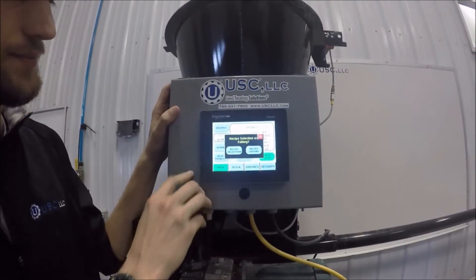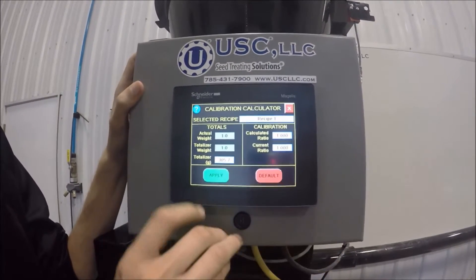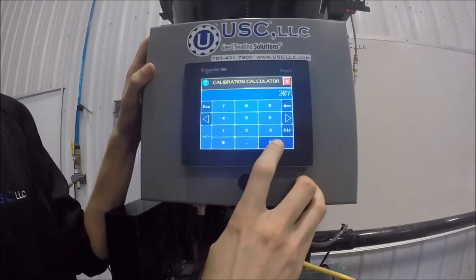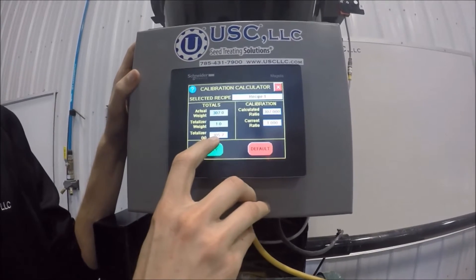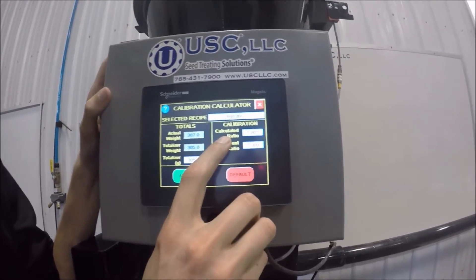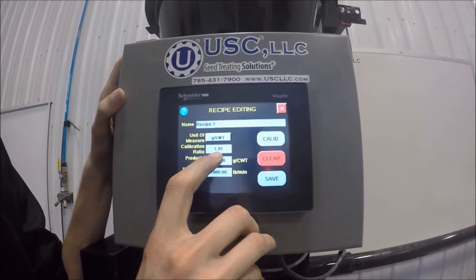At this point, we need to go to Recipes, Recipe Editing, select the recipe we have, and go to Calibration. Our actual weight is going to be the weight we caught — that was around 307 grams. The totalizer weight is going to be what the totalizer number shows here, which says 305, so we put that number in as the totalizer weight. Once we have those numbers entered, we'll see the calculated ratio is updated, and we need to hit Apply to update the current ratio. Now we can see the calibration ratio is updated to 1.01, so we can hit Save.